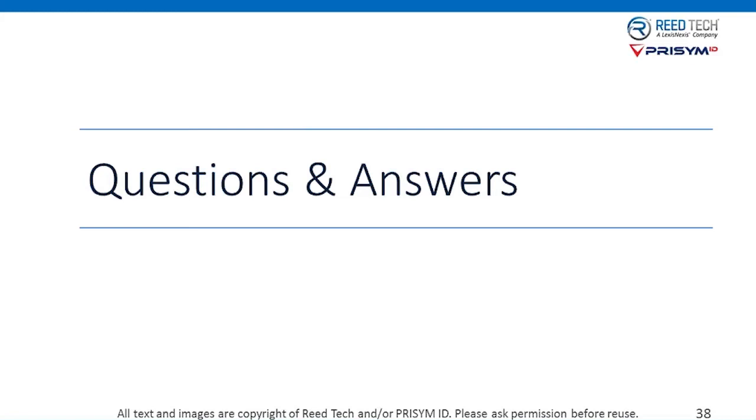Well, you've got your validation requirements that you need to start thinking about. It's never too early to think about your validation requirements. This is a large, complex project, which is subject to change in the future years. So as you start to build your requirements for your system, you should be starting to put together your validation master plan on how you intend to use this system and this process within your environment. Now, whilst you're creating this plan, consideration should be made on how you're going to leverage information from the various different suppliers that you will be using.